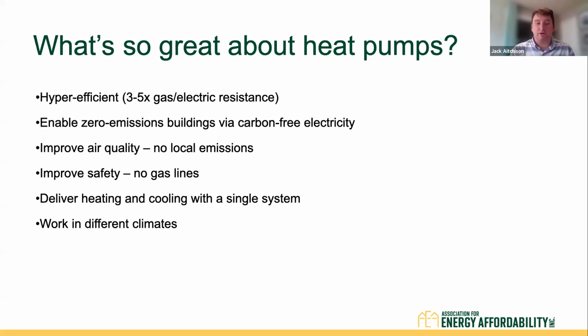It improves indoor air quality and outdoor air quality. You're not going to have any combustion in your building. It improves safety, with no gas lines. Really the key here, and what we'll be focusing on in this presentation, is delivering heating and cooling with a single system. On your HVAC side, if you have cooling in a mixed fuel building, you're going to have 2 separate systems. With a heat pump, you can do heating and cooling with one system, which is going to reduce your maintenance needs. And heat pumps can also work in different climates. A lot of folks say that because heat pumps draw heat from the surrounding air, cold climates may not be a good application. Heat pump technology now can operate as low as -30 degrees. So unless your area is often falling below -30 degrees, you can find a heat pump that's going to meet your application. Next slide, please.